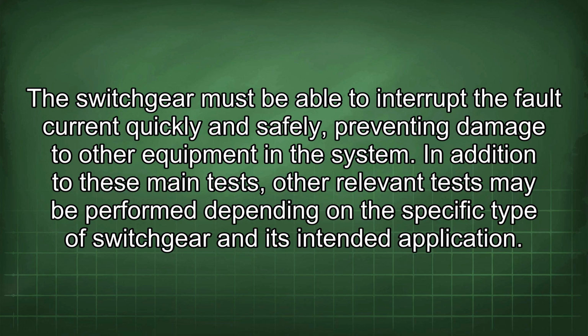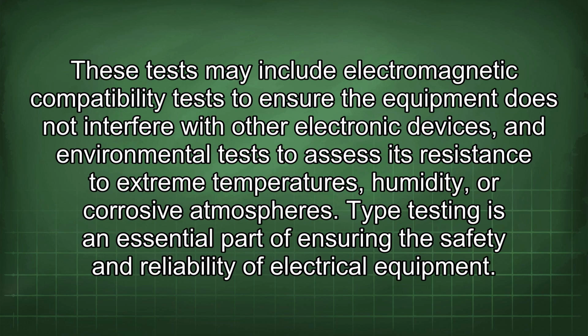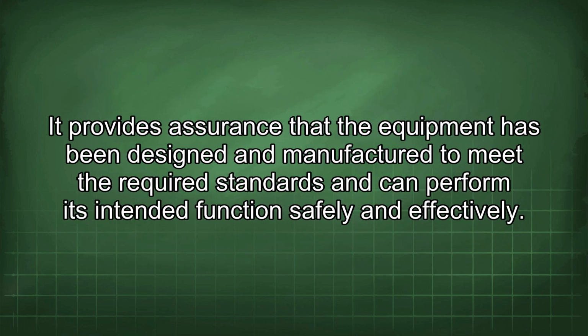In addition to these main tests, other relevant tests may be performed depending on the specific type of switchgear and its intended application. These tests may include electromagnetic compatibility tests to ensure the equipment does not interfere with other electronic devices, and environmental tests to assess its resistance to extreme temperatures, humidity, or corrosive atmospheres. Type testing is an essential part of ensuring the safety and reliability of electrical equipment. It provides assurance that the equipment has been designed and manufactured to meet the required standards and can perform its intended function safely and effectively.